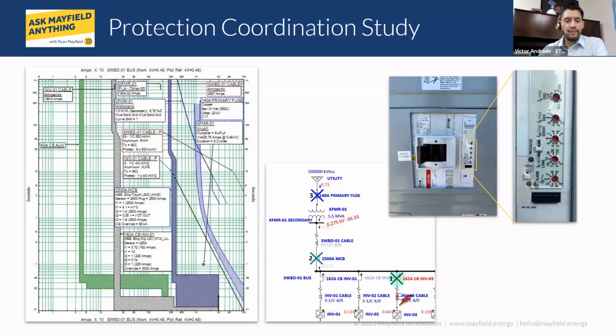And just a quick addition to this, the curves that Nick is showing on the left-hand side are preloaded with the software. These are the time overcurrent characteristics. These are published by the manufacturer, and they tell the protection engineer, in the event of a fault, how long they will take to trip. So it's our job essentially to move the setting dials that you see on the right-hand side to make sure there is no overlap. So in the event of a fault, there is a spacing between them so that we know for certain that the system will be coordinated.